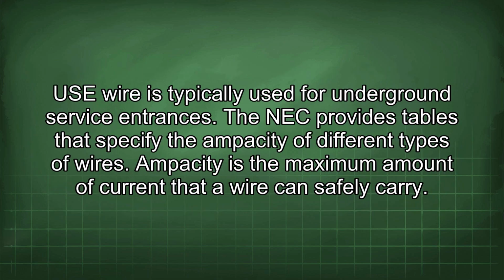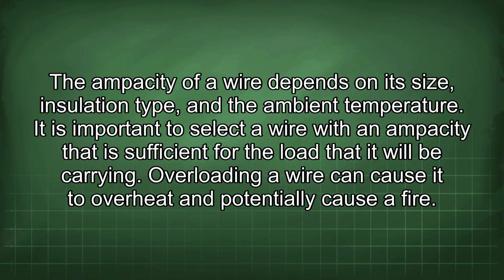USE wire is typically used for underground service entrances. The NEC provides tables that specify the ampacity of different types of wires. Ampacity is the maximum amount of current that a wire can safely carry. The ampacity of a wire depends on its size, insulation type, and the ambient temperature. It is important to select a wire with an ampacity that is sufficient for the load that it will be carrying. Overloading a wire can cause it to overheat and potentially cause a fire.